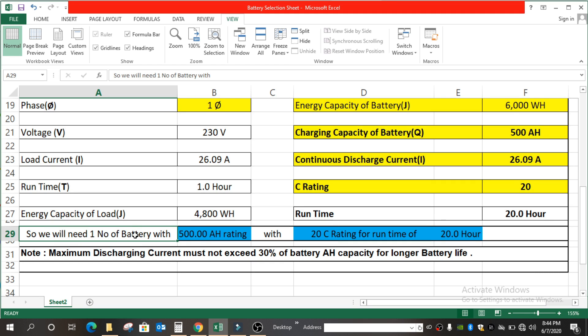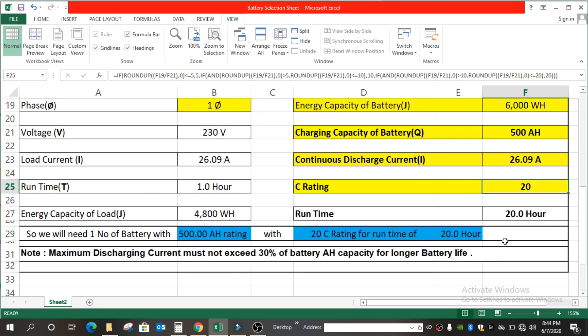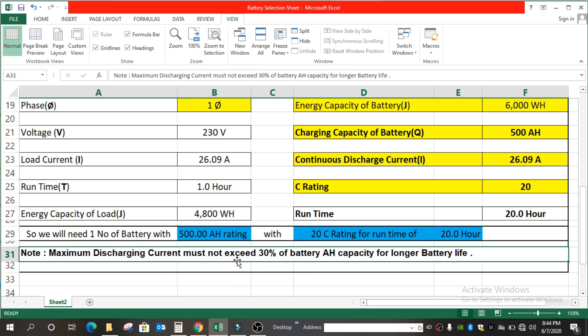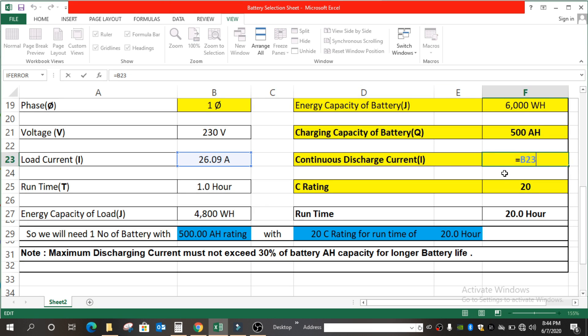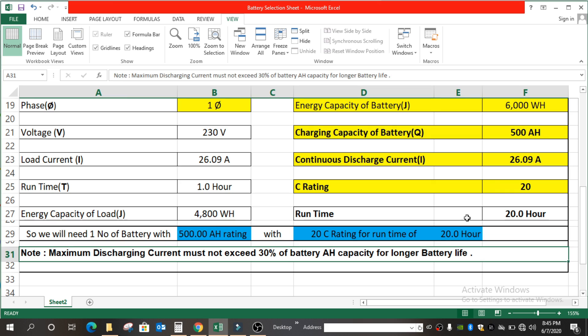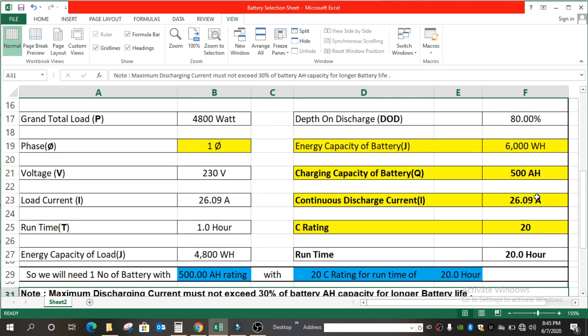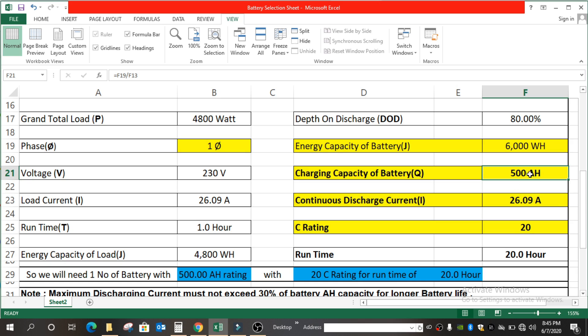Now for the conclusion: we will need one battery with 500 AH rating and C20 rating for a run time of 20 hours. One more important thing to note: maximum discharge current must not exceed 30% of battery AH capacity for longer battery life. The discharge current here is 26.09 ampere, which must not exceed 30% of 500 AH — that is around 150 ampere. In this case, we are not exceeding that limit.